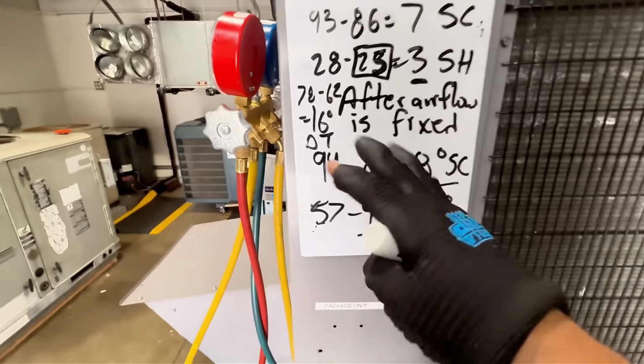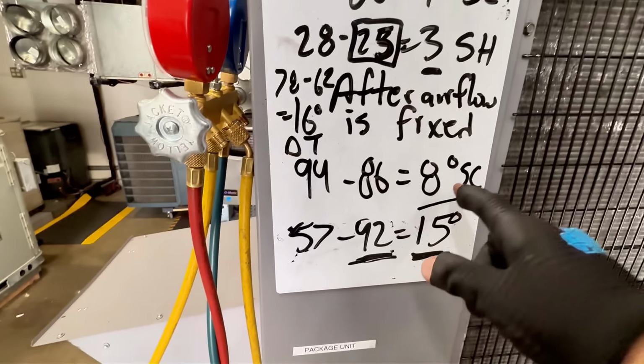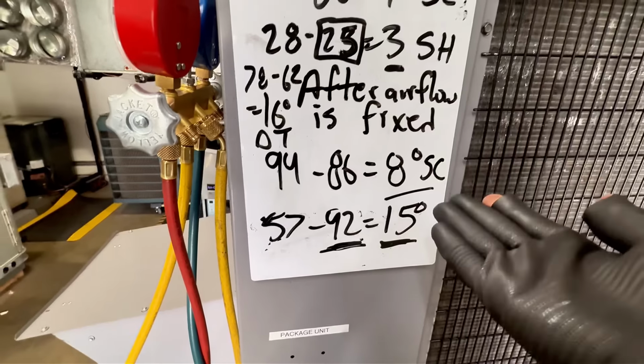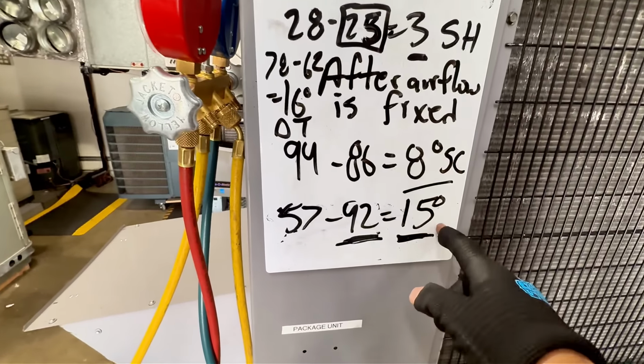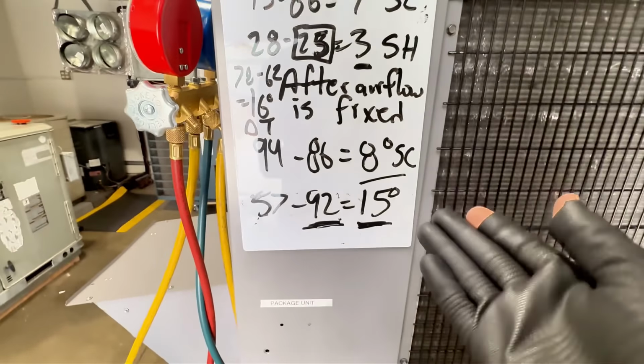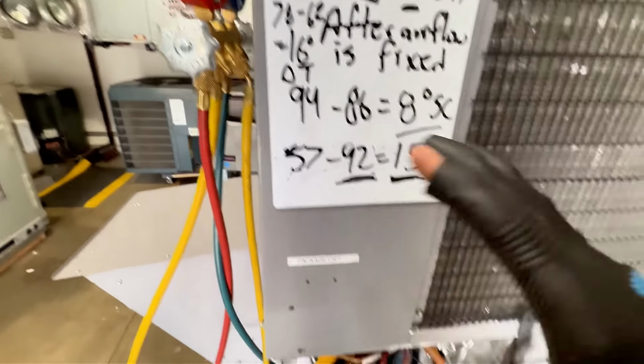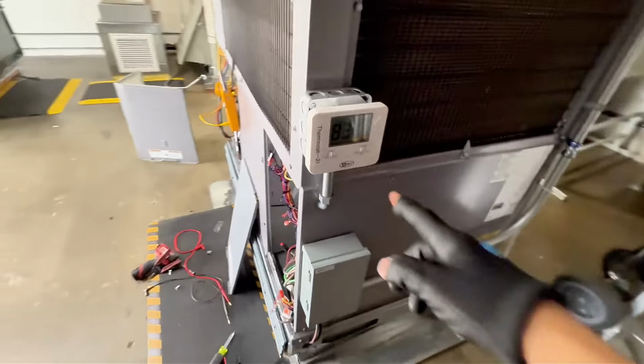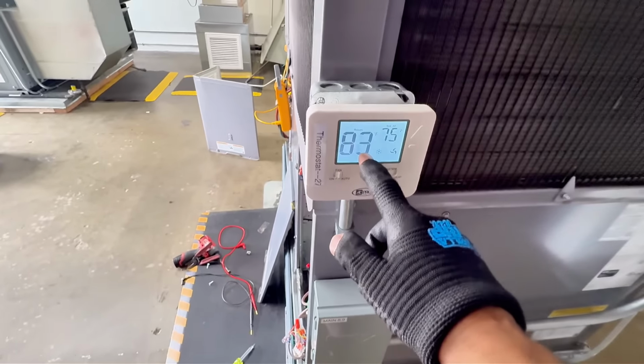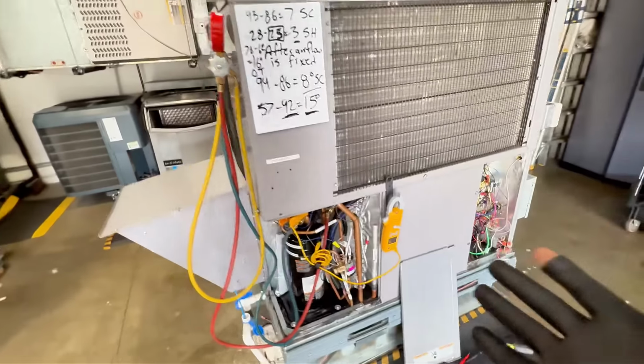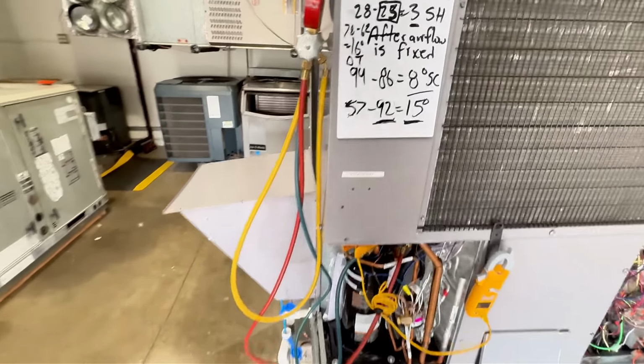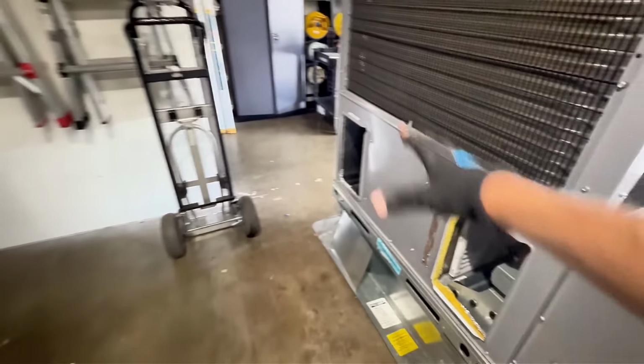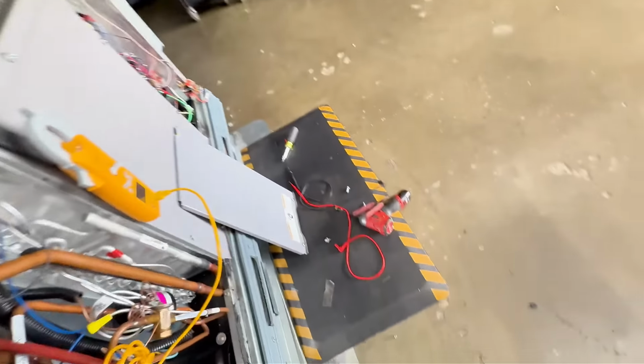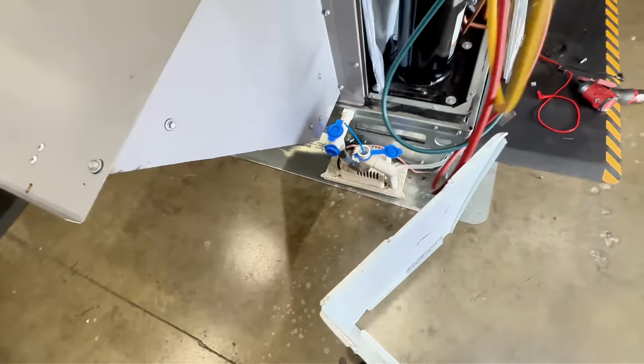I can live with that. You want 18 to 21 delta T. My subcool, you could technically push it up to 10. And this might drop a little bit, but honestly, it doesn't really make a difference because I do have 8 degrees of subcool. The unit's already engineered for it to work like that. It is kind of warm. It is 83 degrees. And obviously this is more of a controlled lab. We have heat coming from everywhere, and you do have that open return, a little return and supply. And there goes that panel, which I'll put back later.